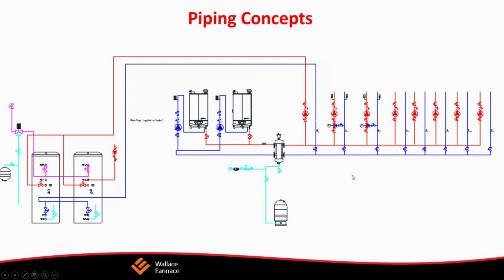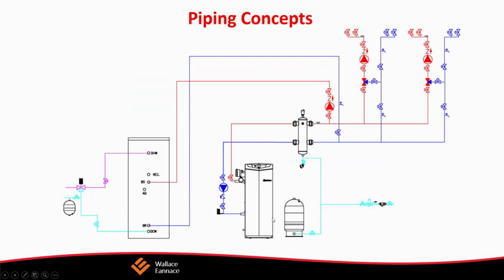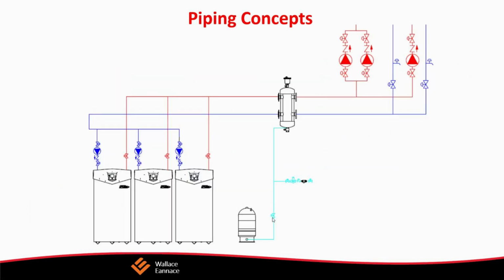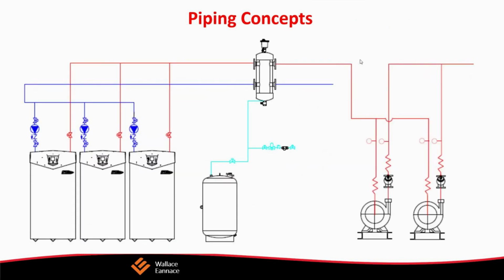So take a look at our typical near boiler piping. And here's one for a combi boiler. And as you can see here we used a primary secondary header. You have your expansion tank, your system pump, you have zone valves going out. Here's your feed valve. You'd have a backflow preventer here. And that would all be on the heating side. On the domestic hot water side, you would have a domestic hot water mixing valve, a domestic hot water expansion tank. And if you find this, I mean, people who install this are pretty comfortable with it.